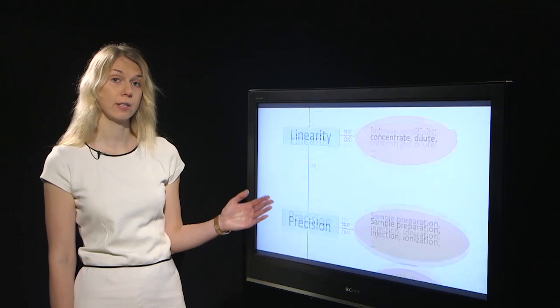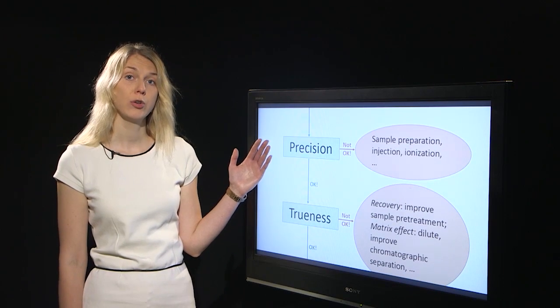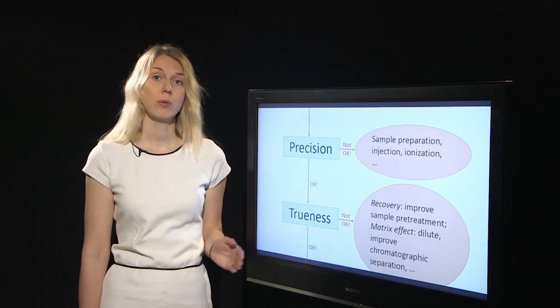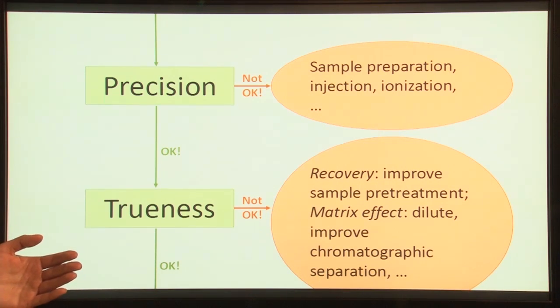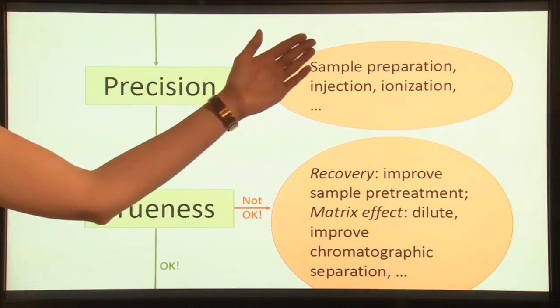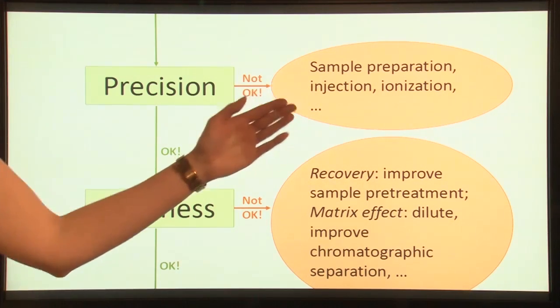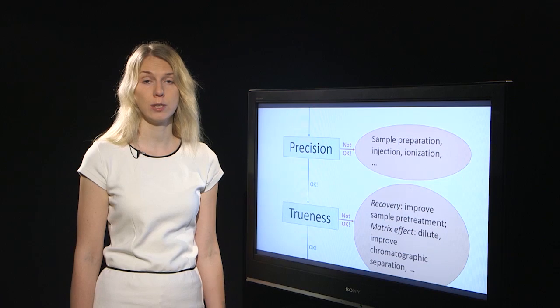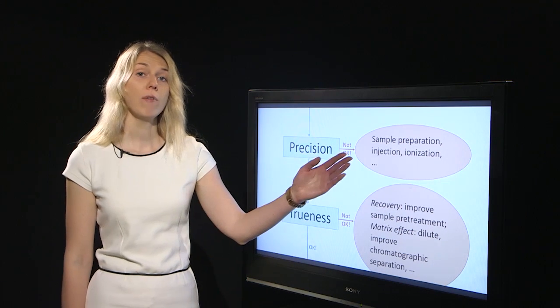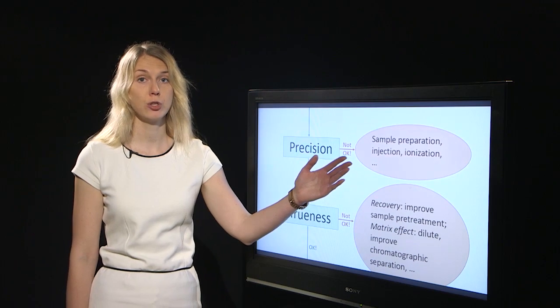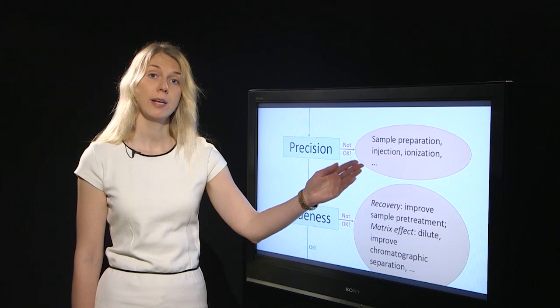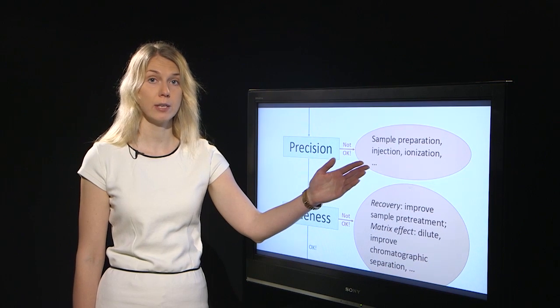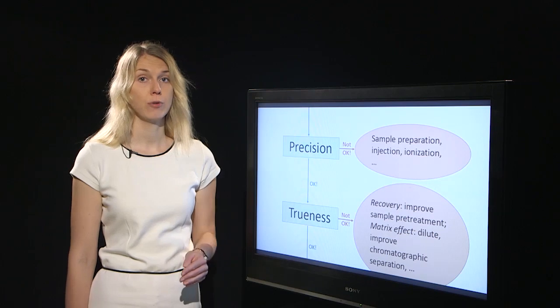However, if linearity is acceptable we can move on with the validation to precision. If for some reason the precision is not acceptable, first you should try to find out which part of your method causes this inacceptability — does it come from the sample preparation, from the injection, or is the problem in the ionization? If you have found the root cause of poor precision, then you should make modifications to that specific part of your method. However, if modifications are made, these may significantly influence previously evaluated validation parameters and you should start the validation from the beginning.